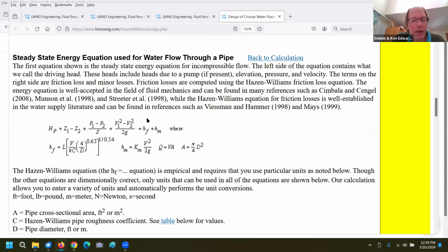So basically the fundamental equation is the same as using Darcy-Weisbach, which I showed you on the previous screen, but your friction loss equation is different. So here's the friction loss equation for Hazen and Williams. This may or may not look familiar. You can see it in different forms. Sometimes it's shown in terms of diameter, sometimes in terms of length on the left side, and they'll combine some of these coefficients and maybe use different units. I believe this diameter is in feet, the head loss is in feet, and velocity is in feet per second. But there are plenty of equations out there with diameter in inches and with different coefficients.